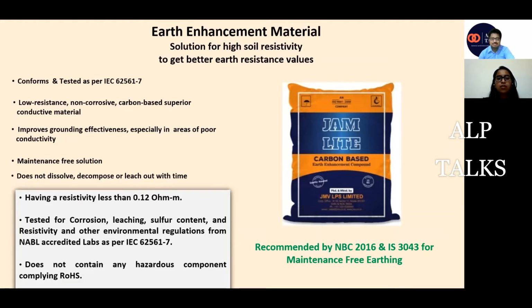This is the compound which I was talking about, the chemical which is making the complete system maintenance free. Basically, as per Indian standards and as per the National Building Code, the compound or chemical which we are using for our earthing system shall have a resistivity of less than 0.12 ohm meters. This value has been mentioned in the standards. The compound or artificial treatment should have a value of less than 0.12 ohm meters, and it should be tested as per IEC 62561 part 7.